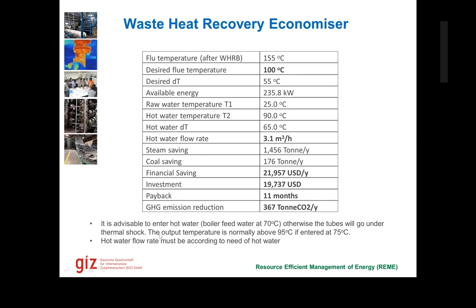It is advisable to feed hot water to this system, not directly cold water. So we can use a little bit of a water preheating system at around 70 degrees Celsius, and then we can get water at around 95, or even if it is a pressurized system, we can get water at 100 degrees Celsius. If it's a non-pressurized system, then 95 to 98 degrees Celsius is easily recoverable. But this hot water flow rate must be according to the need for hot water. If we don't have any need of hot water in the process, there is no need to install the system, unless we can use it in the boiler, for example, for feed water.